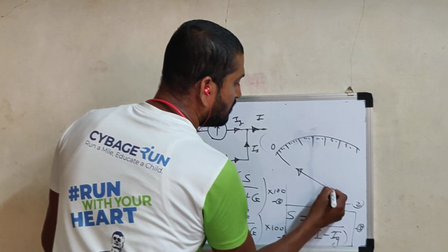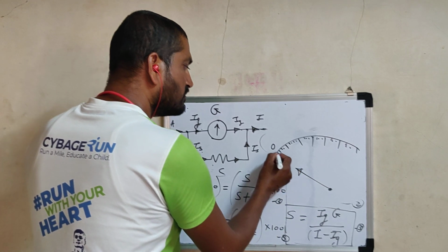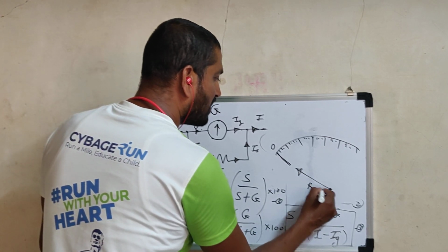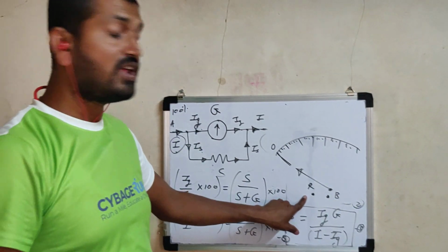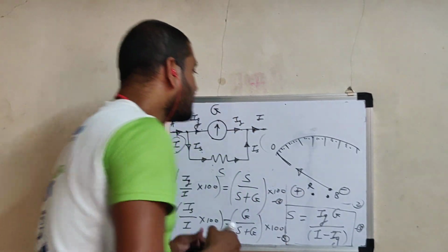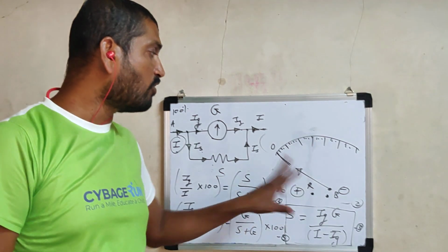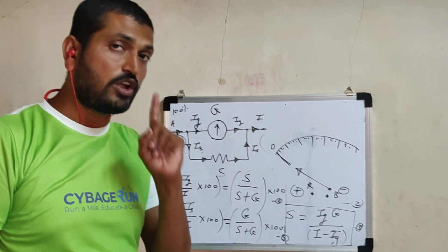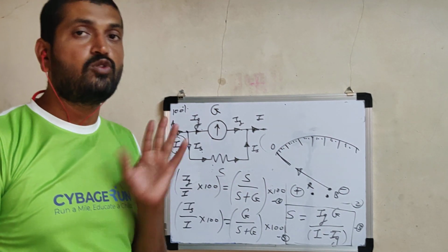When no current flows, the pointer shows 0 deflection. Now due to the 0th marking on the left side, 2 polarities are compulsorily marked here, red and black. The red terminal is the positive terminal, while black is the negative terminal. So while connecting the device, no doubt the ammeter is always connected in series, but the precaution to be taken is that the red terminal, meaning positive, must be connected to positive, while the black terminal, meaning negative, must be connected to negative.